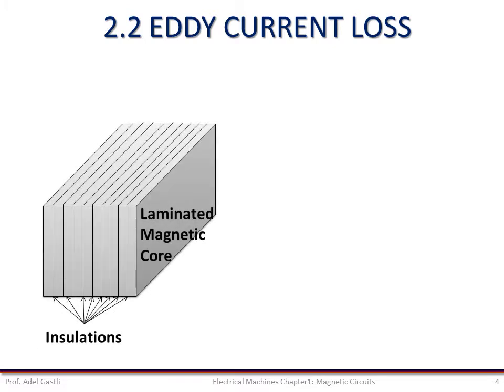The eddy current loss can be reduced in two ways. A high resistivity core material may be used, or addition of a few percent of silicon — say 4% — to iron will increase the resistivity significantly. Another way to reduce the eddy current loss is to use a laminated core. The lamination is made in the plane of the flux so that the current path is cut by the insulation layers, which makes it difficult for the eddy current to build and circulate.